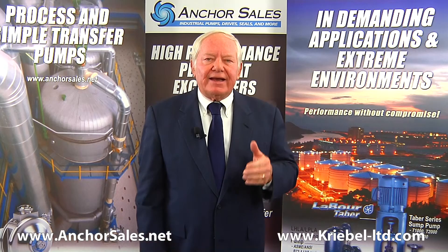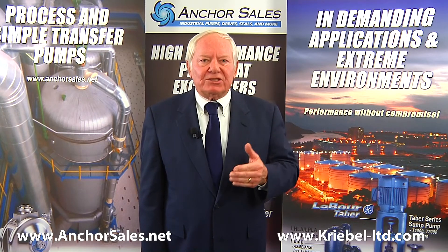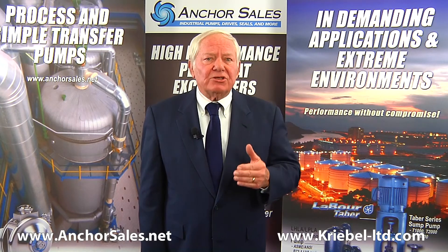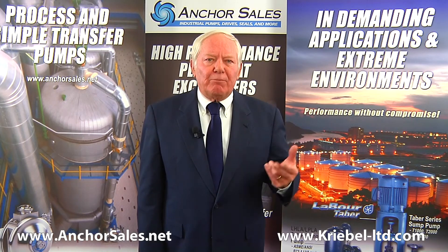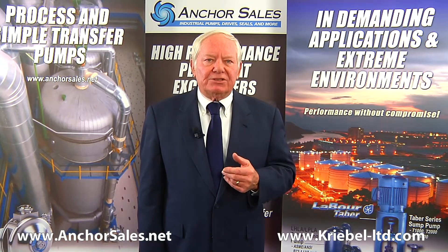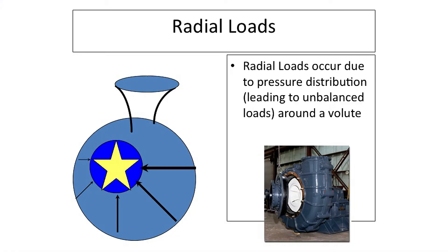This could set a minimum flow based on axial loading. Designers minimize axial loads with balance holes, back rings, and pump-out vanes. Similarly, centrifugal pumps generate radial loads due to load imbalances around the impeller. This is due to volute geometry. The pump designer tries to minimize radial loads at the best efficiency point.